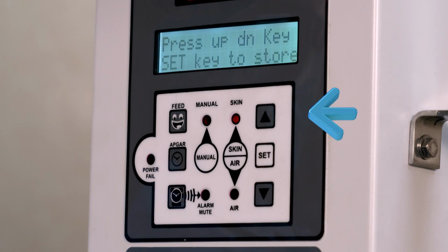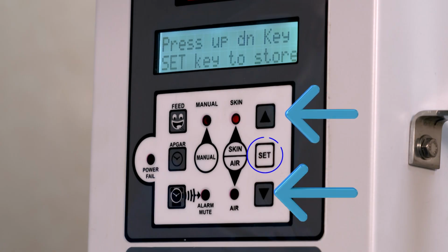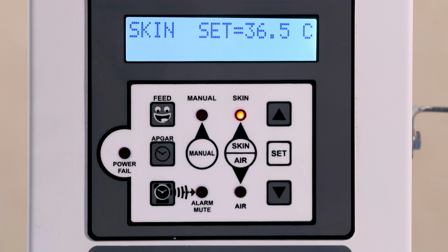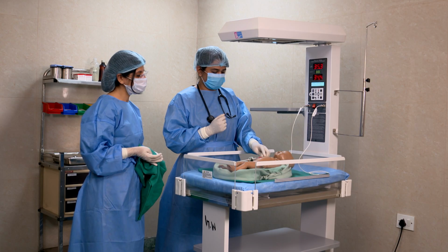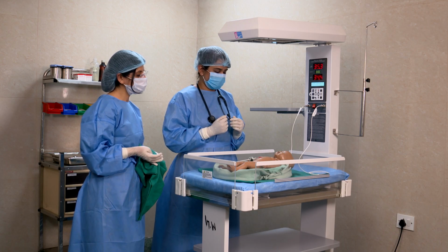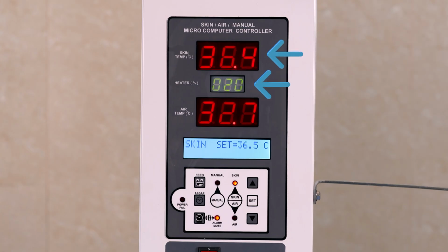Always remember to set the desired temperature of the neonate to 36.5 degrees centigrade in the control panel while using the servo mode. This will help to regulate the amount of heat being dissipated by the warmer to maintain the baby's temperature.